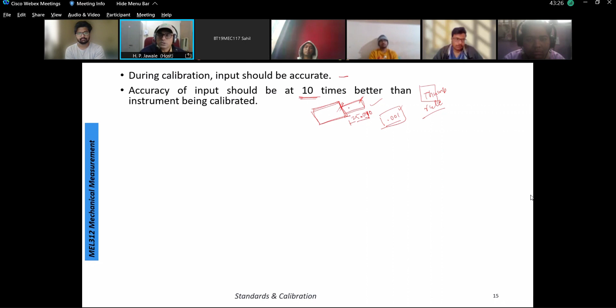So with this very obvious understanding, we have a thumb rule that the accuracy of the input should be 10 times better than the actual measurement or the instrument that is to be calibrated. From the measurement point of view, I told you that the job of 25.01 is to be measured. I must have a vernier caliper or micrometer screw gauge which is more accurate than these 2 decimal points. So it is desired that it should have accuracy up to the third decimal. Same thing applies here. Suppose this is now the element under calibration, this steel rule. Suppose I have a steel rule with me and I desire that the accuracy of the steel rule is up to 2 decimals. Then definitely the instrument that is used for checking this steel rule should be more accurate, minimum 10 times more accurate than the steel rule that is being calibrated.